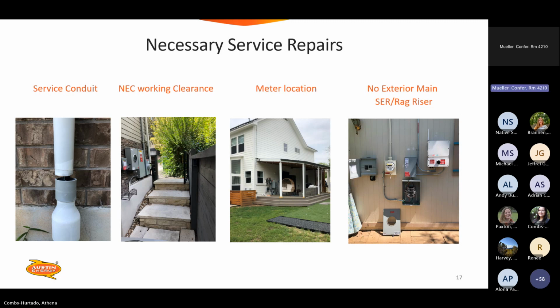And then that last picture, there are two different problems with that if you look closely. One is that there's no main breaker. That's the revenue meter that we can see with the actual meter in it, and then it goes directly through that wall to a breaker panel inside the house. Austin Energy will require an exterior main disconnect before it feeds the loads into the house. So that's one thing in that picture. The other thing is that that's a SER/rag riser. So if you see a service that has a rag riser like that, it definitely needs to be replaced as part of your PV installation. Next.